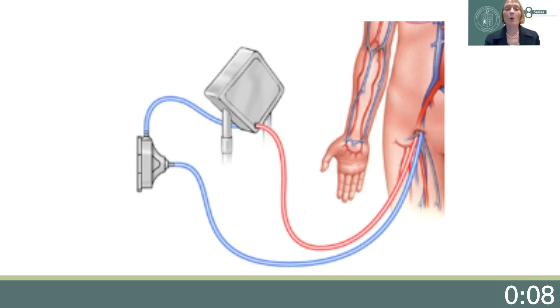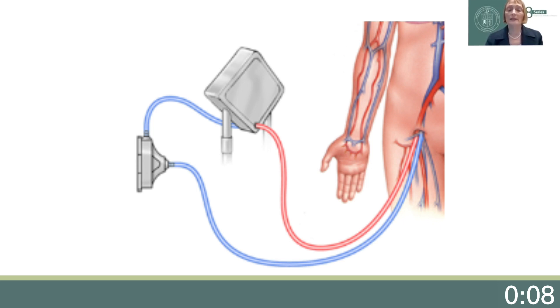It's important to realize that the ECMO circuit, like the cardiovascular system, perfuses the body based on pressure and flow. Therefore, the clinical team must be familiar with normal pressures and flows of the ECMO circuit, variances of these normal circuit pressures and flows, the causes of the variances, and interventions to quickly resolve these variances.